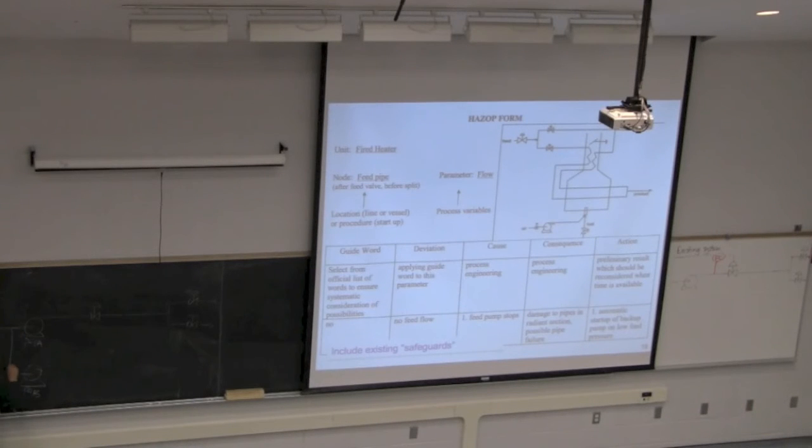Okay, so same feed over here. Do we put a valve in here? Yes. No. What if that valve is closed? Do we really need that backup pump? Right, so the moment we put a valve in here, remember this pump is going to come on automatic startup of the backup pump. So if this valve is closed, we're just going to ruin the pump and actually not achieve anything.